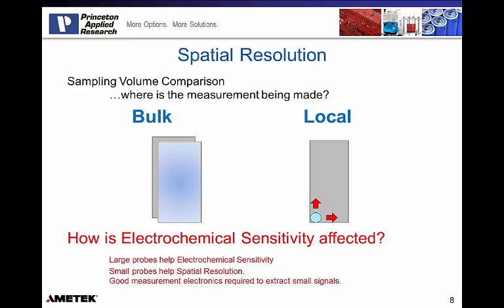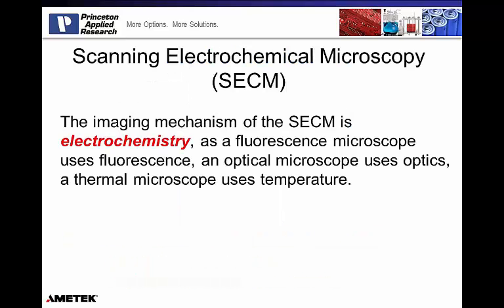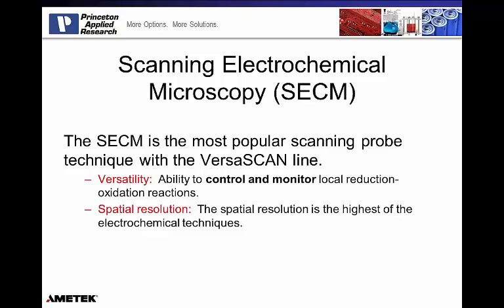So if I take the word SECM and break it down, it's a scanning electrochemical microscope, or the technique of scanning electrochemical microscopy. The imaging mechanism here is electrochemistry. What we like to say is that as a fluorescence microscope uses fluorescence as its technique to image, an optical microscope uses optics, and a thermal microscope uses temperature, this electrochemical microscope is going to look at the electrochemistry happening at your sample. And that's very exciting for us because no other technique is going to be able to give you localized electrochemical information the way you would with an SECM.